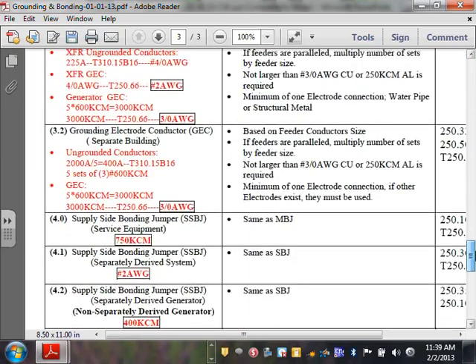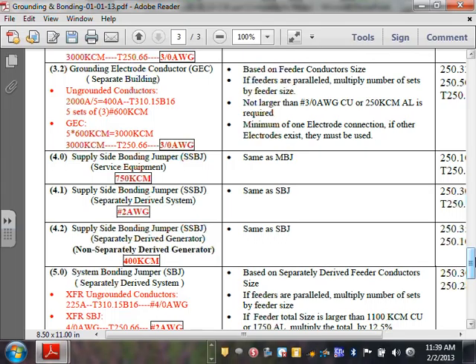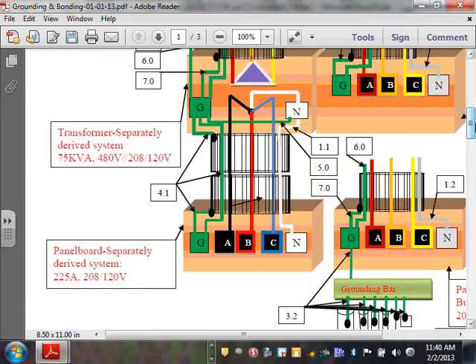Just look at 4.1, if you don't mind. 4.1, guys, it's a supply side bonding jumper, separate derived system. And can you guys see what I said here? Same as system bonding jumper. System, not main. You see the difference? Main at the service, system at the separate derived system. Any comments, guys? Any questions about that? So what you end up doing here is you end up pulling an equipment and a supply side bonding jumper conductor, and also bonding your flex with the proper fittings into the enclosure on both sides.